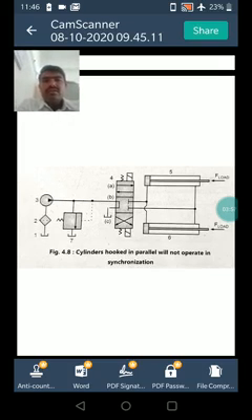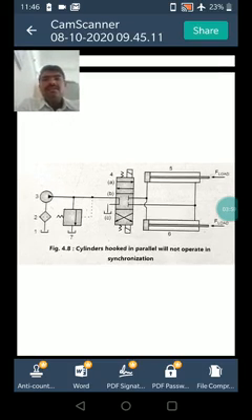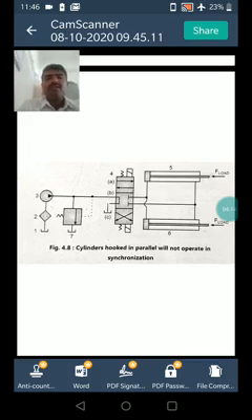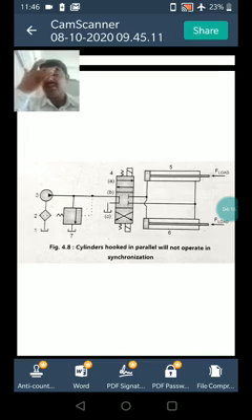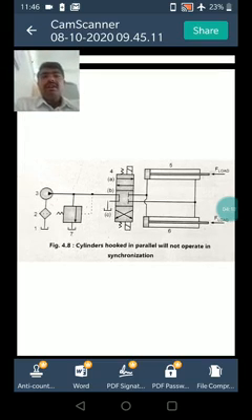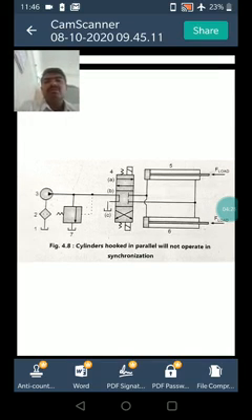In that, the loads on these identical cylinders must be equal to achieve exact synchronization. Many times the loads may not be exactly equal. In such a case, the cylinder with the lower load would operate first, at lower pressure. Only after this cylinder has reached its end of stroke does the pressure build up further to the higher level.